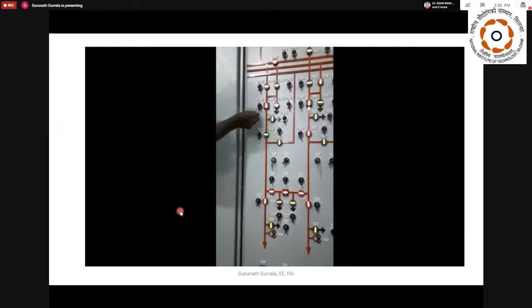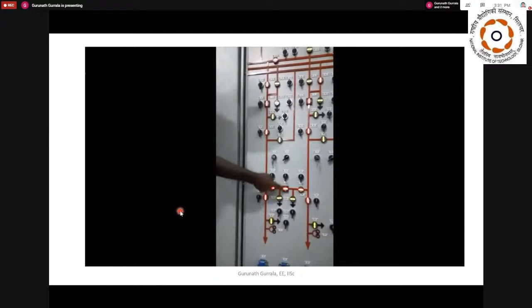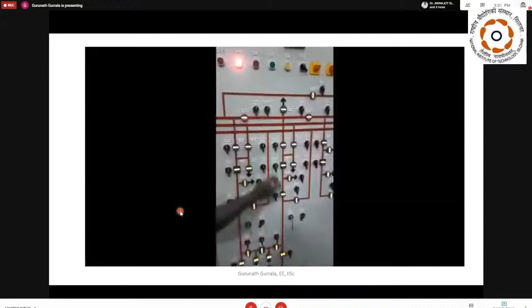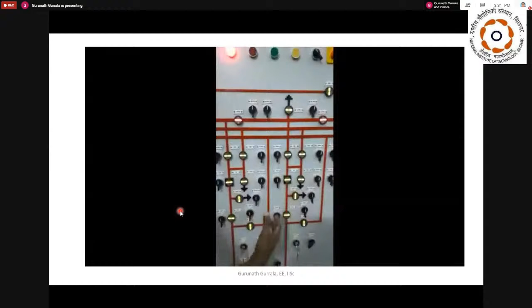Now if I close these two, these two are closed, now I will not be able to operate. So if you put it into breaker and off, the isolators related to transfer bus or double bus will not be operating. I will show that this isolator, which is not operating, I will try to operate and show that it will not operate. See, this one is not operating because it is selected to breaker and off.